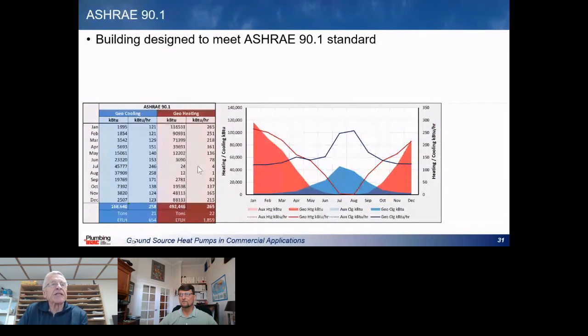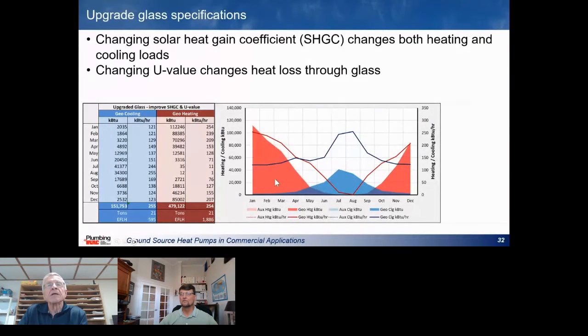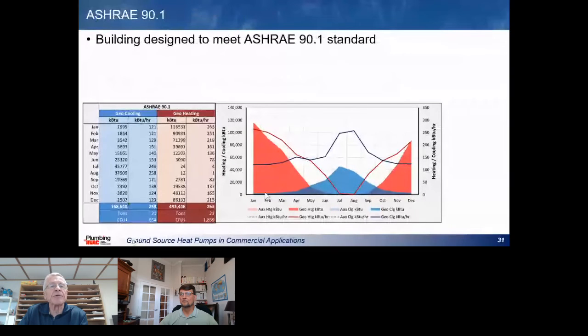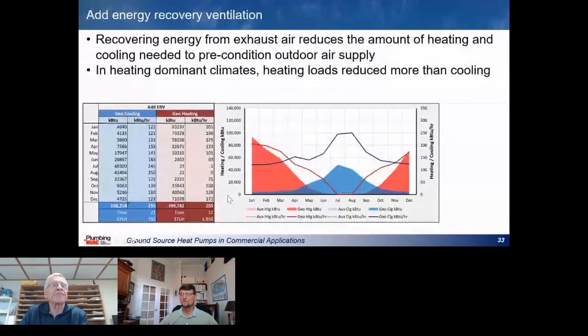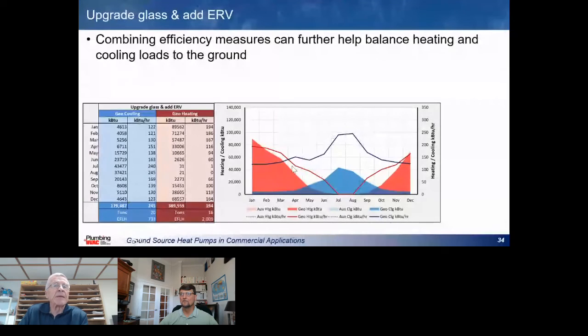So as an example, you can see the energy load profile. Here's how much energy this particular building is using, 23,000 square foot building. Here's what that looks like for peak heating loads, peak cooling loads, annual heating requirements, and annual cooling requirements. So if we change the glass on there, that changes the loads a little bit. Here we're looking at 22 tons. We've knocked the ton off there, and it changes the loads a little bit, and it changes the energy balance. If we add an energy recovery ventilation system, now we're down to 17 tons of heating, and the cooling stays about the same, so it changes the energy balance on it. Add both of those efficiency measures, that changes it again. And it's a really building specific kind of technology. Look at unique features of a given building that might help to balance the energy loads.